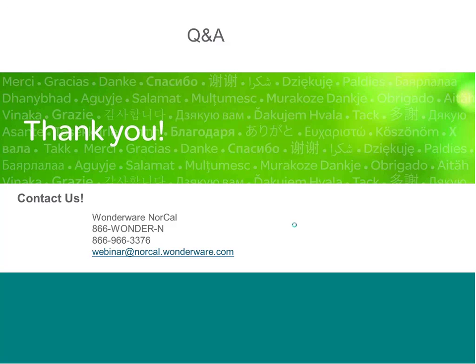Okay. The next one is, can Wonderware's latest version support my old PCs? Yeah, that's a good question. Wonderware has been around so long through so many operating systems that we do have official support for, for any given version of InTouch, what operating systems those support. For example, the current version of Wonderware we refer to as 2014 R2, and we support Windows 7, Windows 8, Windows 10, Server 2008 R2, Server 2012, and Server 2012 R2.